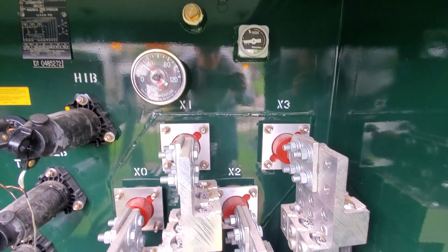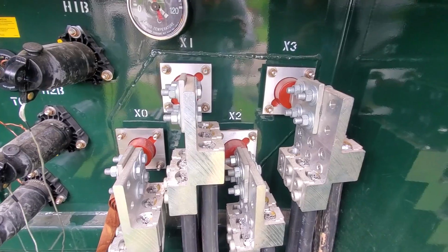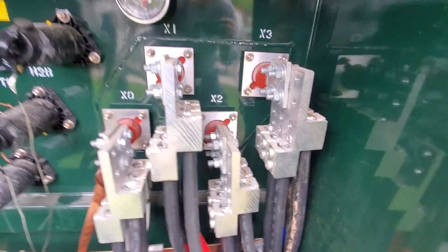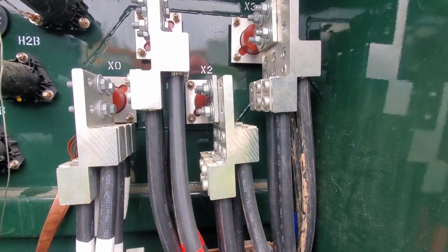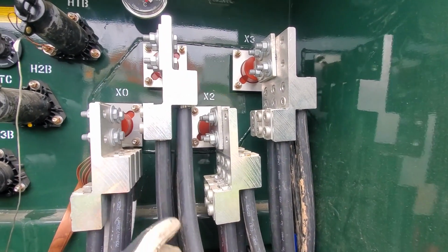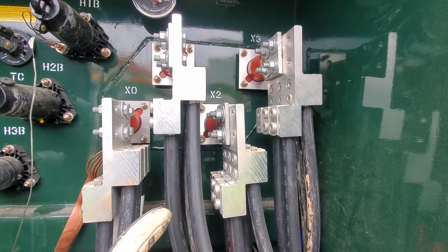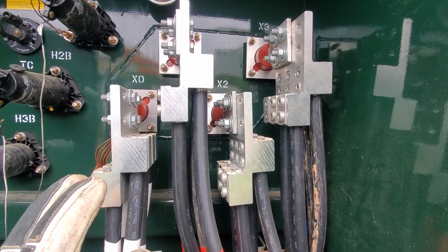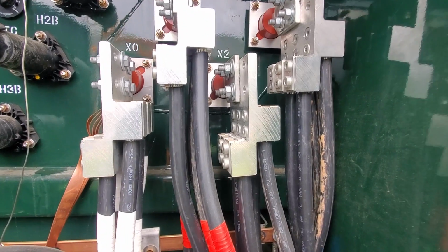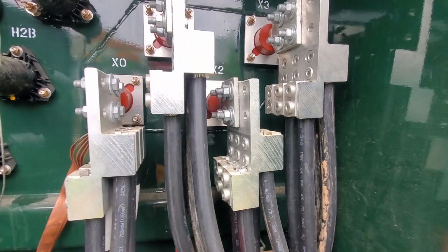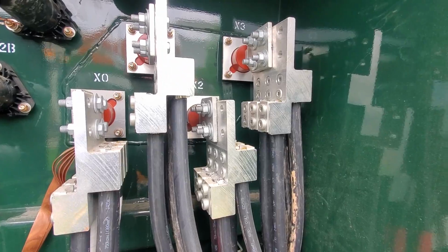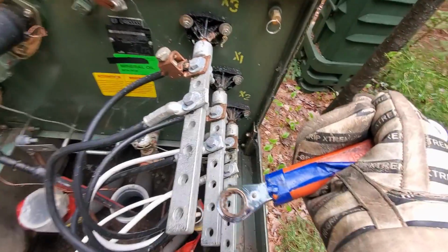We don't typically have a whole lot of problems with pad mount transformers anyway. Now, a pad mount like this, we're not going to start taking any of this stuff apart live - it's just way too congested. The cables are large, with 6 cables running off of each one of those bushings. However, in the video where we had a lot more space, it was easy to work with while energized.